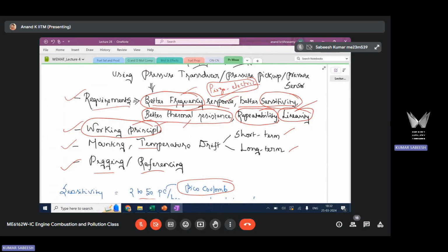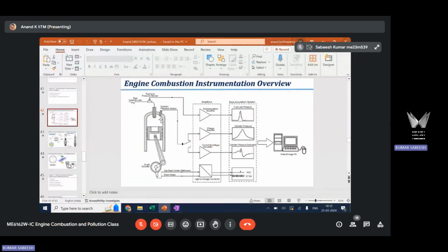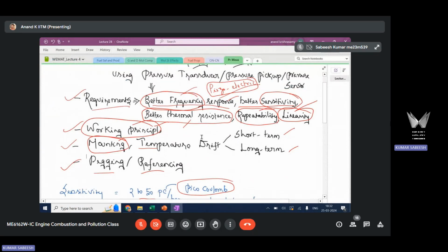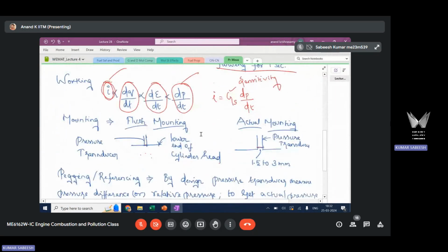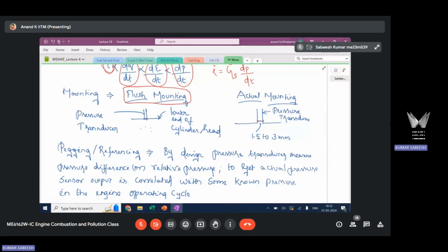So this is how the sensor works, and with respect to mounting, we mount the sensor in the cylinder head as shown here in the schematic. Where we locate it is an important point to be considered. One of the important aspects when we mount the sensor is that it is preferable to use what we call flush mounting. What is flush mounting? You can see that the bottom end of the sensor diaphragm aligns with the lower end of the cylinder head. This is what I mean by flush mounting. This is preferable because you are exposing the diaphragm directly to the in-cylinder gas pressure, so the accuracy will be higher.